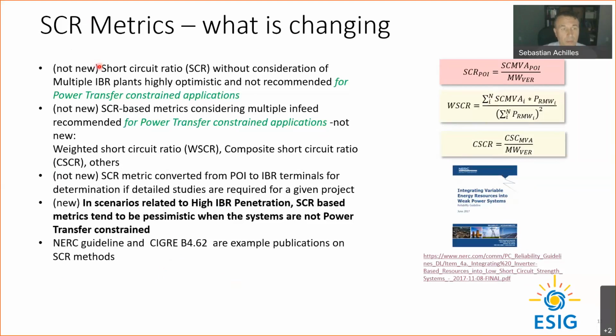A couple of points about how the industry operates in general, most of you probably know this. The calculation of short circuit ratio without consideration of multiple inverter-based resources is highly optimistic and not recommended. If you have an area with many inverter-based resources planned close to each other, and you calculate the short circuit ratio of one plant while ignoring the others, you'll get very optimistic results. That's been discouraged for a long time. SCR metrics that consider the multi-in-feed are recommended.